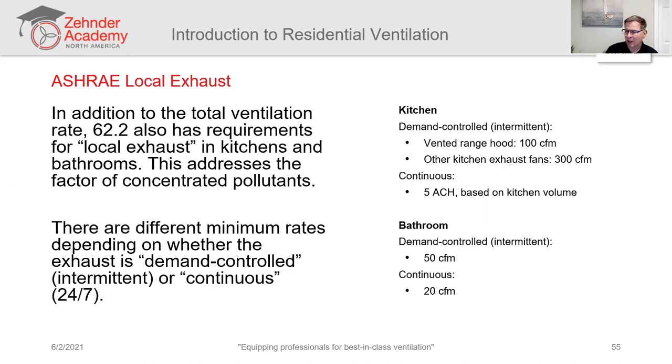Just as a side note, most bathroom exhaust fans that are rated at 50 CFM, by the time they get hooked up to a piece of flex duct that gets snaked around joists and run in a figure eight, and deposited out of a soffit outside of a house, that's typically not going to give you 50 CFM. Just a side note. But the requirement is 50 CFM. However, if you go to continuous 24/7 ventilation, then you can reduce that rate to 20 CFM, but that's running all the time. So these are the exhaust rates.